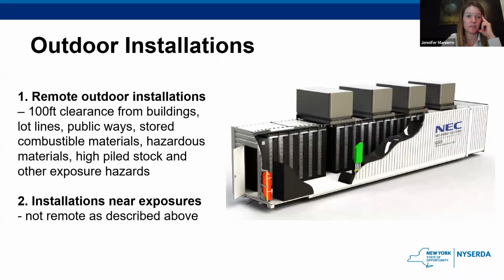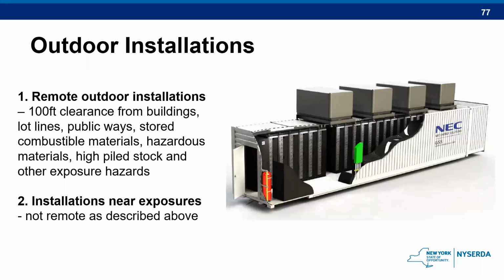For remote outdoor installations, they're remote if they have 100-foot clearance from basically anything that could be a hazard: another building, the lot line in general, any public ways, combustible materials, etc. Any exposure hazard needs to be at least 100 feet away in order for it to be considered a remote installation. Anything else is thought of as an installation near exposures.